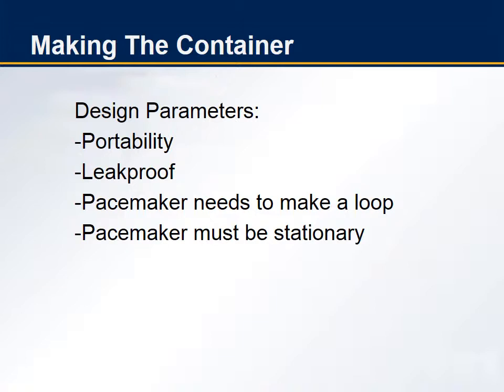Our third parameter was that our pacemaker lead needed to make a loop. Our pacemaker lead needed to make a loop because it would need to mimic the worst case scenario for RFID interference. So when we test it to different RFID readers, we'd have a better chance of interrupting the pacemaker. And last, the pacemaker needs to be stationary while inside the container so we can get consistent results.